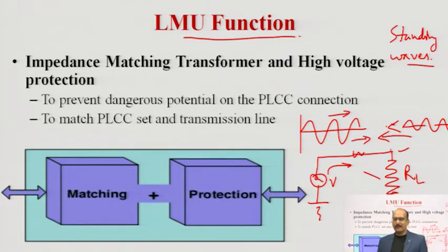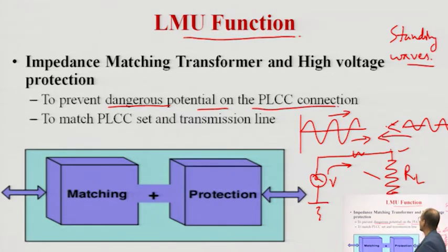These standing waves are basically going to disturb the normal functioning. So, in the line matching unit, what we are going to do is prevent the dangerous potential on the PLCC connection, and also match the PLCC set and transmission line impedance.